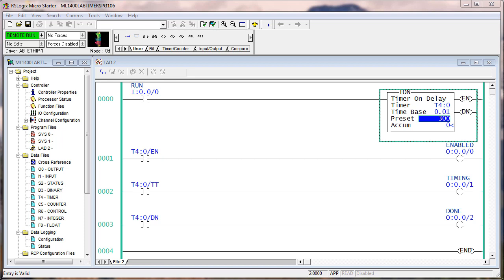When does rung zero become logically true? When input zero is on. Which bits react immediately when the rung goes true? The enable and timer timing bits. From the instant that the enable and timer timing bits are set, how long before something else happens? You could say three seconds, or you can say three hundred hundredths of a second.